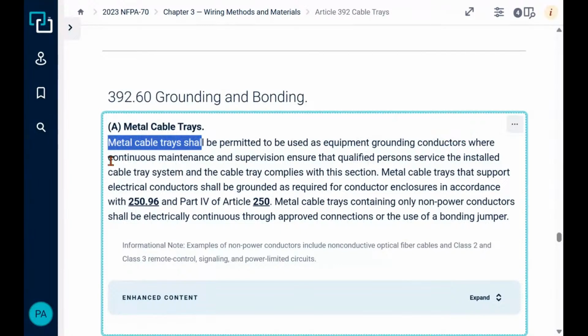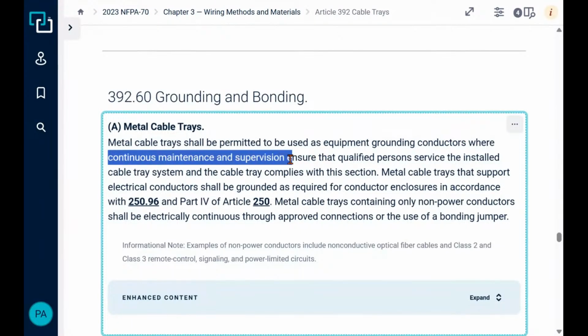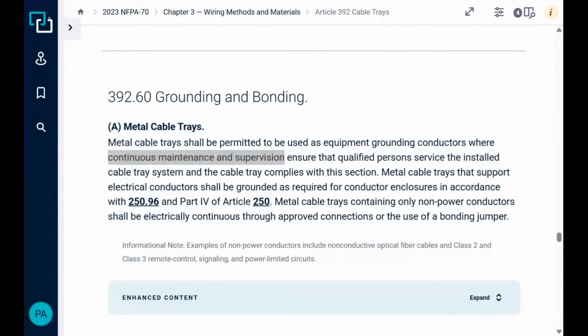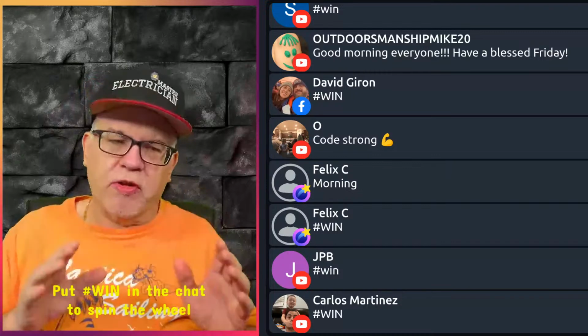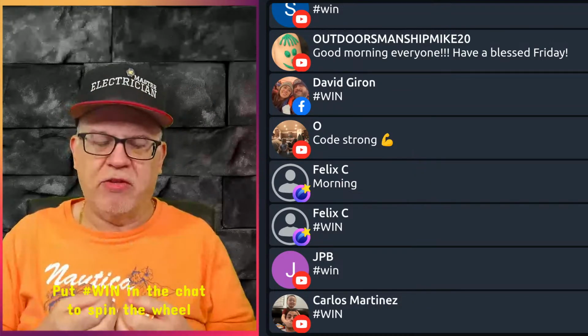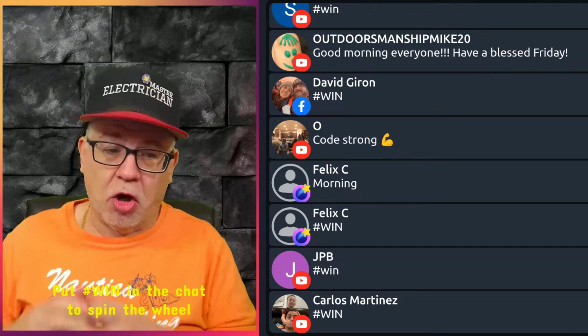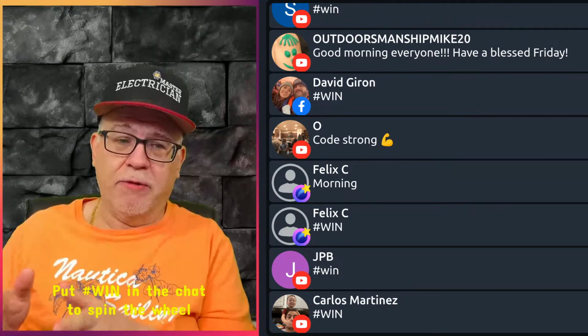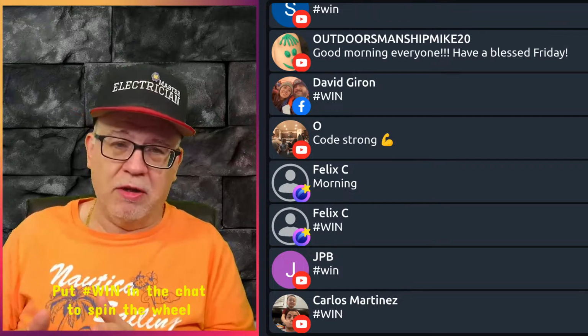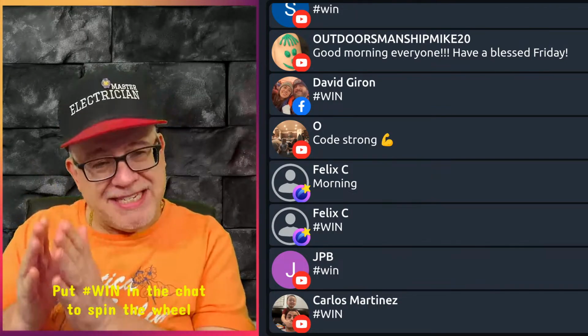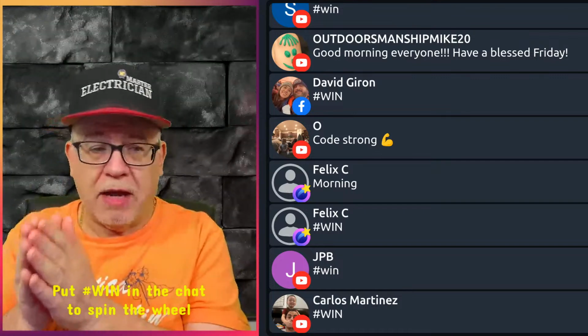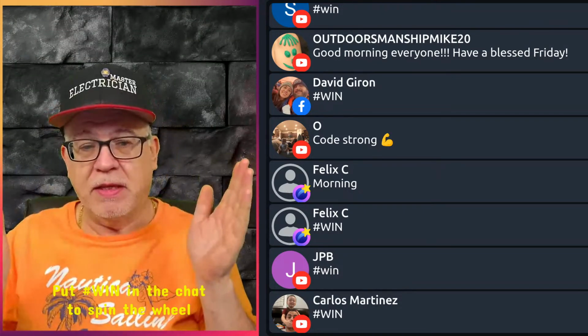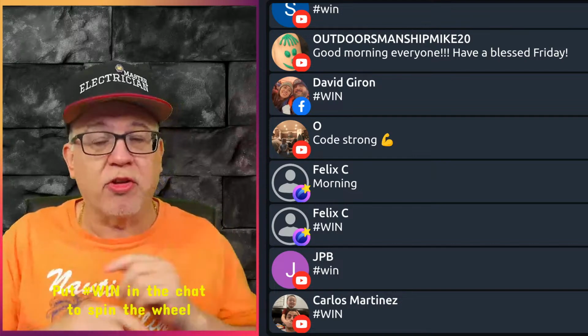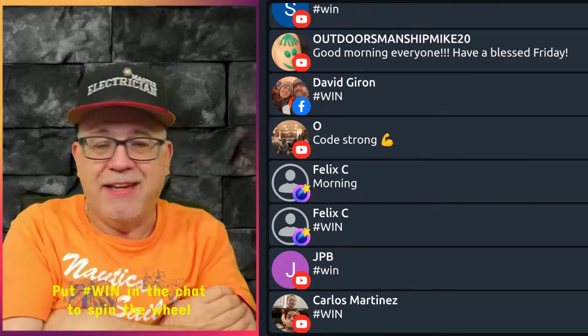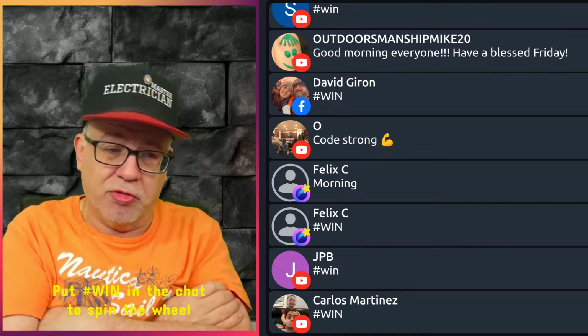It says where continuous maintenance and supervision. Okay, so that means that it's not just your everyday location. If you're going to use the tray as an equipment ground, it's got to be continuous maintenance. It means you have to have a crew. Not like I can call Carlos and have his guys come out and look at it, right? Or Felix come out and look at it when something's wrong, call an electrician. No, it has to have a crew that continuously monitors maintenance and supervision of that system. That's the only way this works. Otherwise, you're going to do probably what everybody else does out there, they just put equipment grounds in it. They don't use the tray, okay?